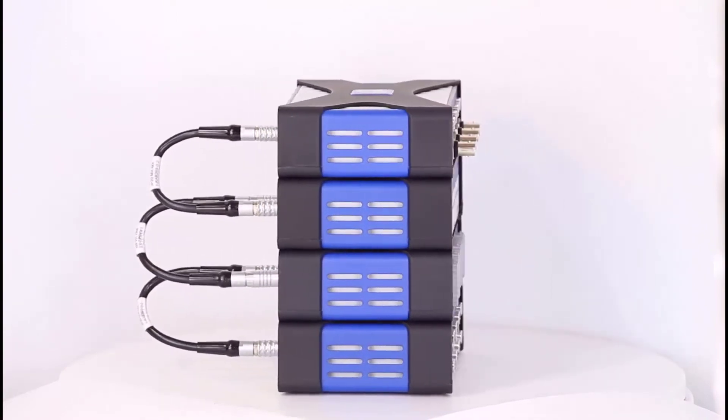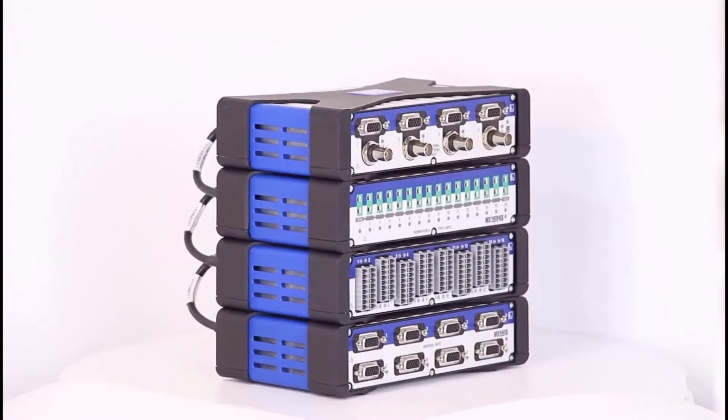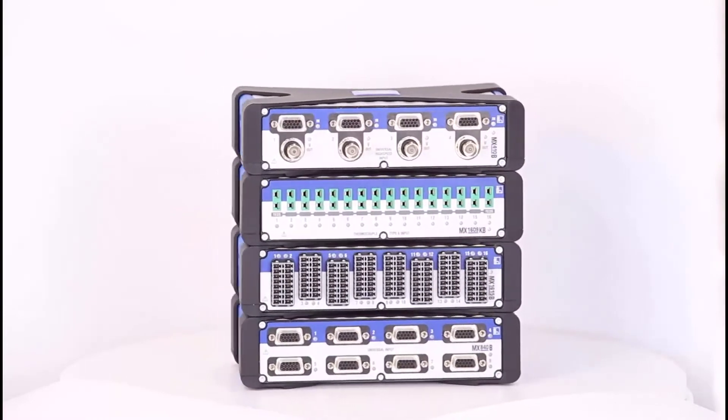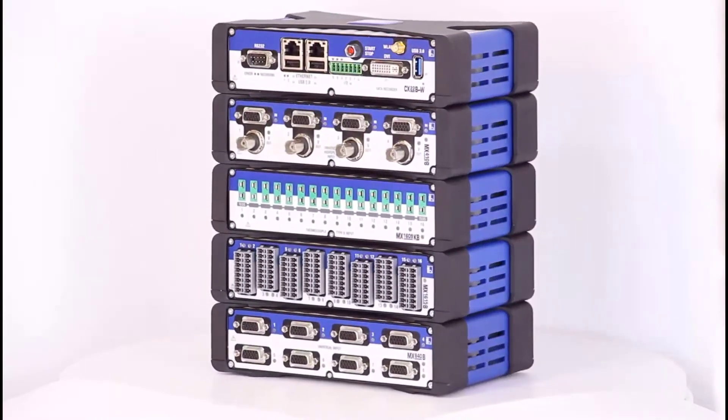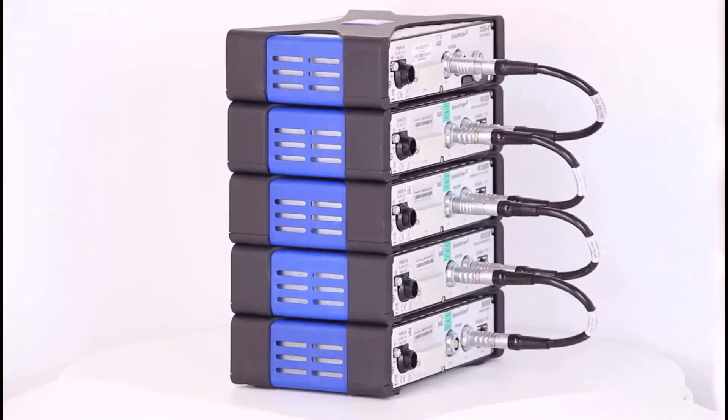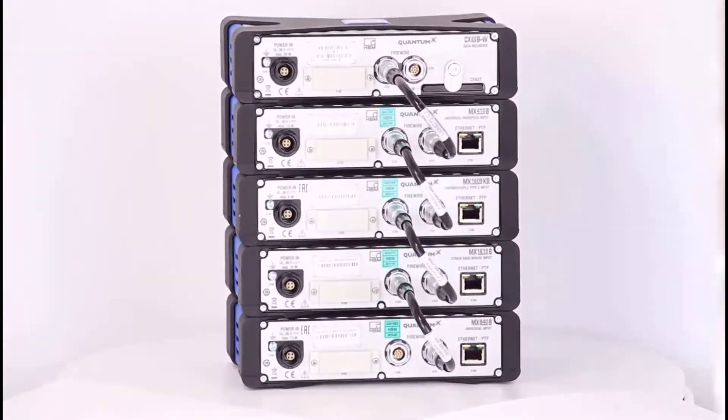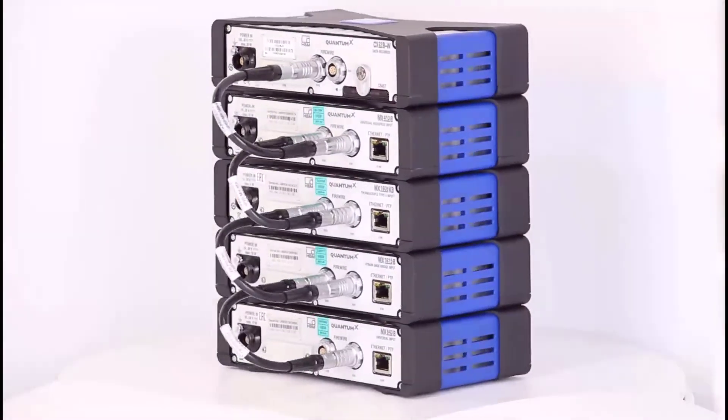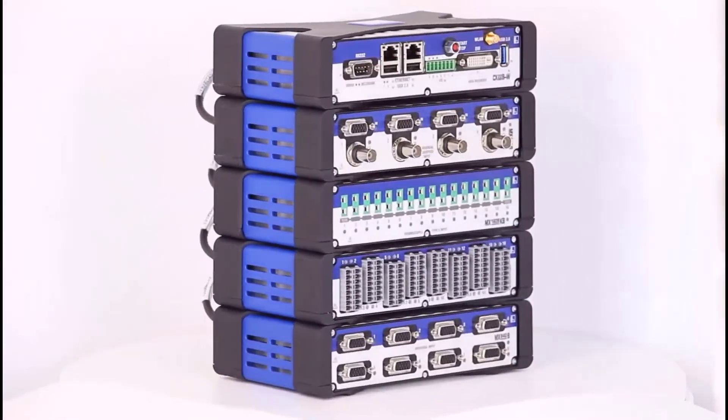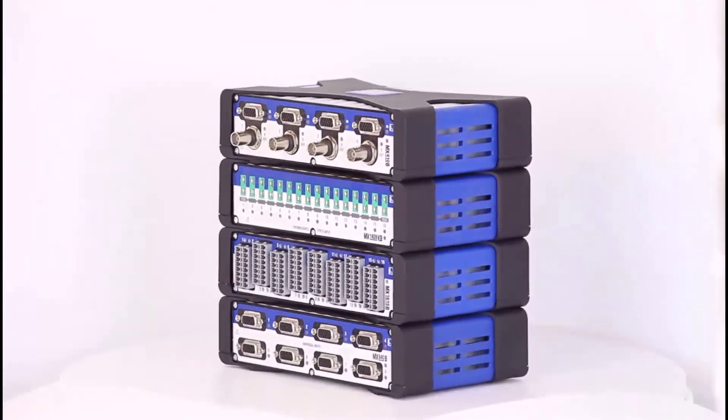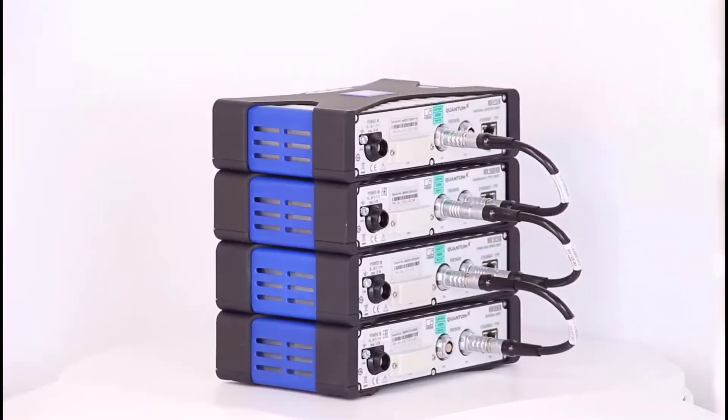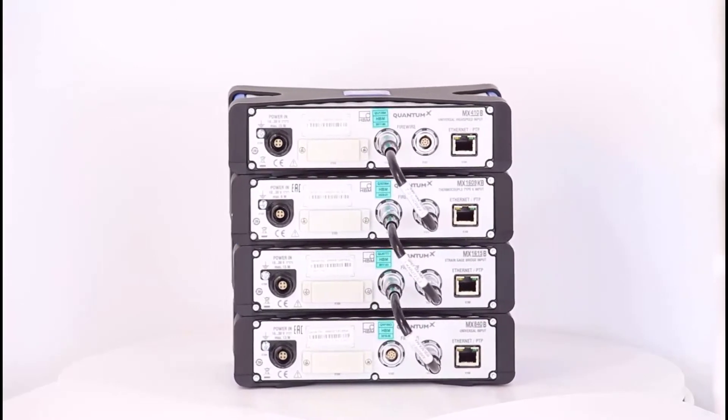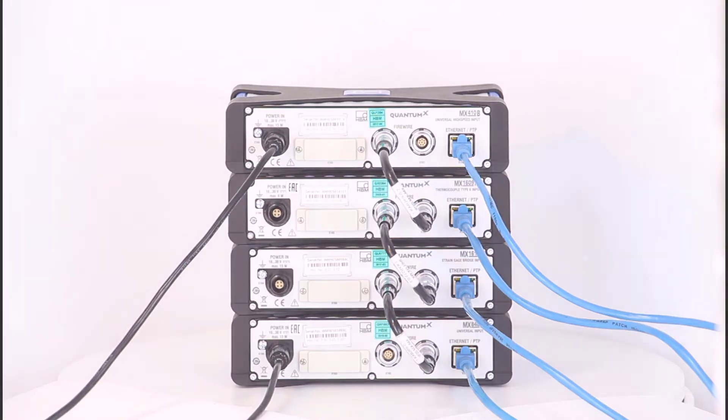Now to the measurement data transmission. If you use the CX22B data logger for data acquisition, simply place it on top and use another firewire cable. The measurement data is then transferred via firewire. If you use a notebook or PC for data acquisition, you should use Ethernet cabling with a switch. I have already connected all the sensors to the modules and connected the modules to my notebook via a switch.